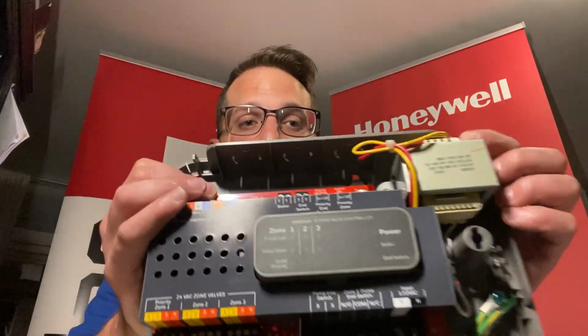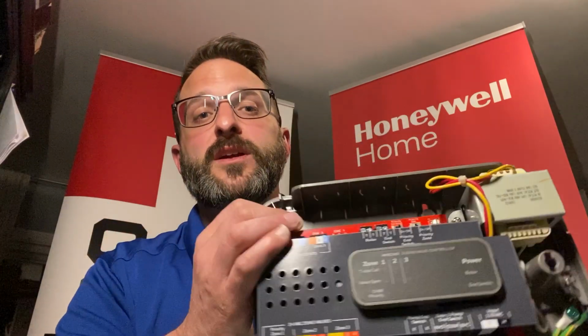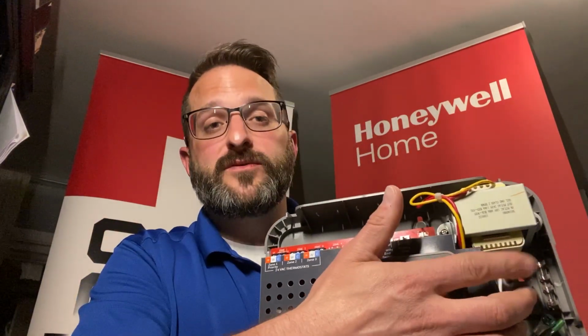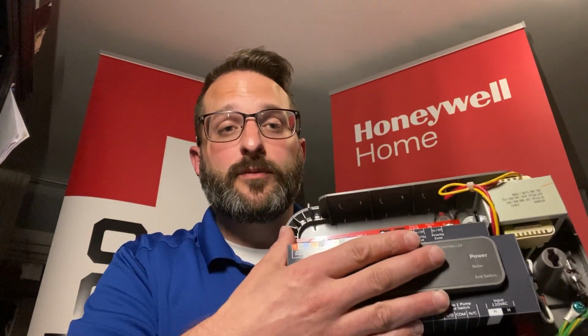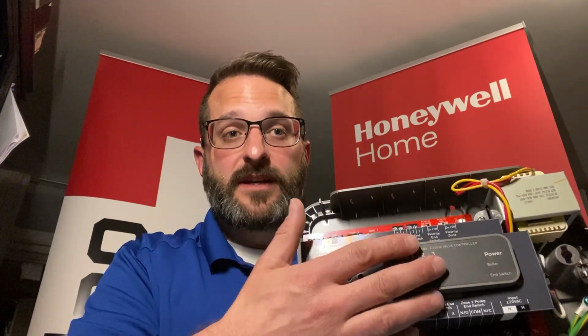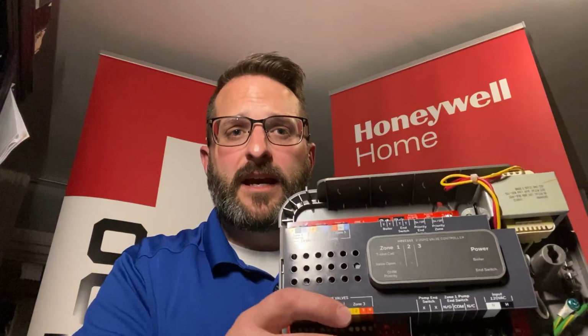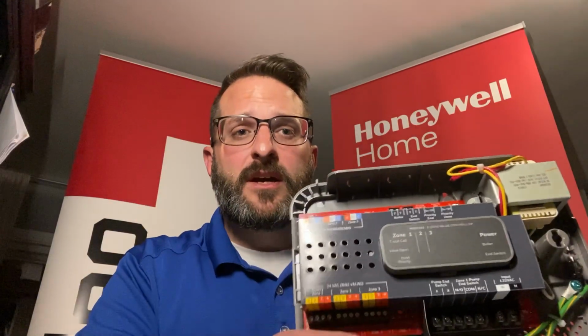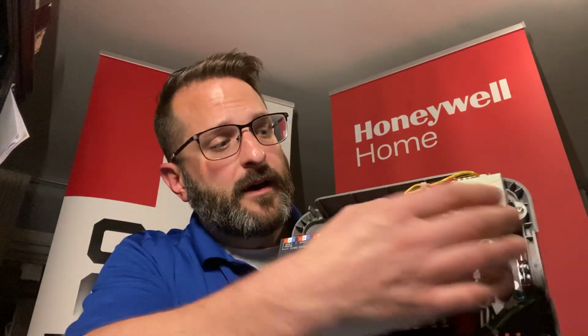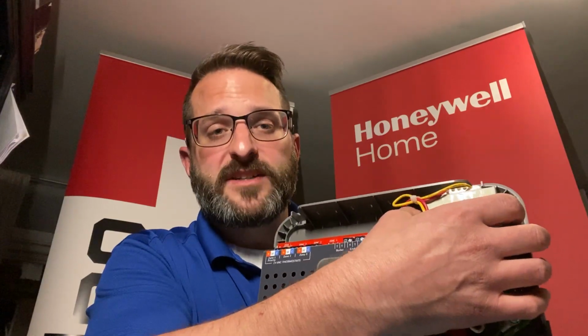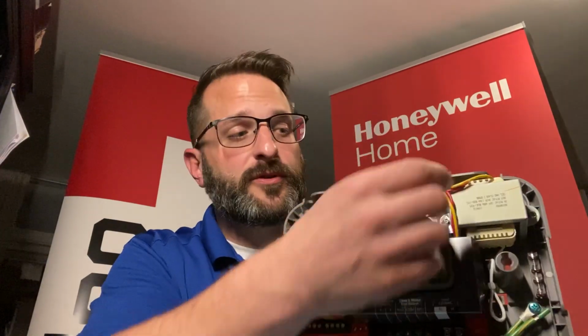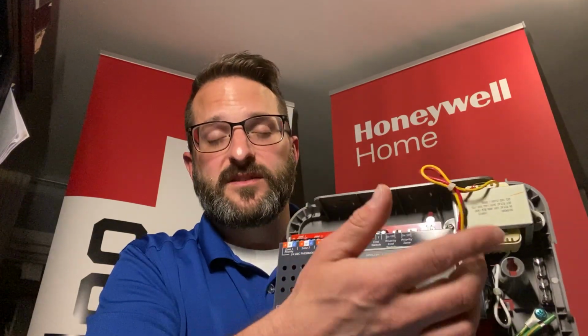So going over to the actual transformer, it's a true 40 VA 24 volt transformer, so we can support 3-wire, wax style zone valves, and we should have enough power to support any kind of system outside of what we're controlling here. This transformer is also replaceable, so we have 2 Phillips head screws, and we gave you enough wire here on the pigtail to replace and splice.